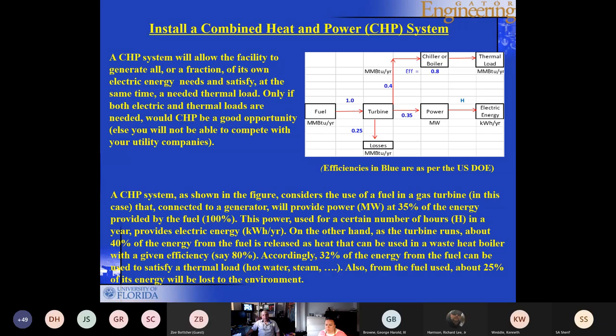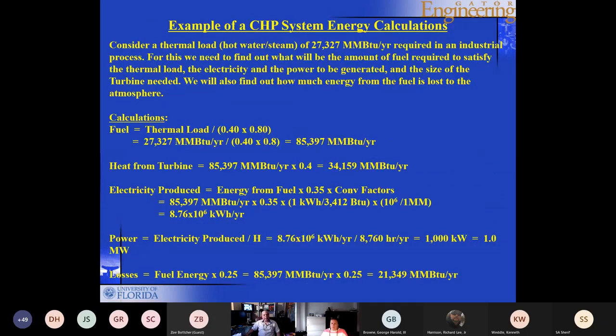And assuming that, from the fuel used, about 25% of its energy will be lost to the environment, we can go to the next slide and see how the calculations are done. You got the thermal load, which is 27,327 million BTUs per year. You divide it by 40% by 80% to get the amount of energy that is going to be needed from the fuel. The heat from the turbine is going to be 40% of that amount, which is 40% of 85,000. You get 34,000.